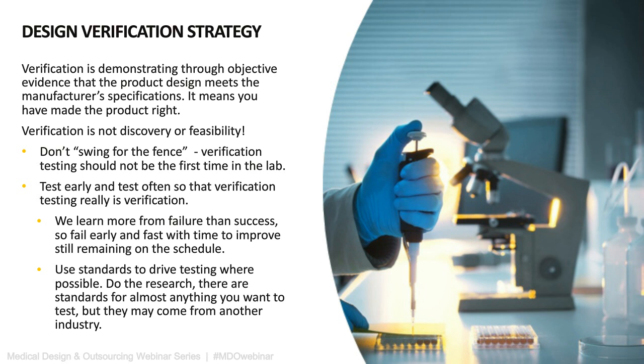As I mentioned earlier, don't swing for the fence in verification. Your testing for verification shouldn't be the first time in the lab. You should be going in there confident that that product is going to pass that verification test. How do you do that? You test early, you test often, and then verification is really just verification. It's not discovery. We learn more from our failures than we do from success. So fail early, fail fast, and leave yourself in your schedule time to improve so that you're not at the last minute going, it doesn't work.